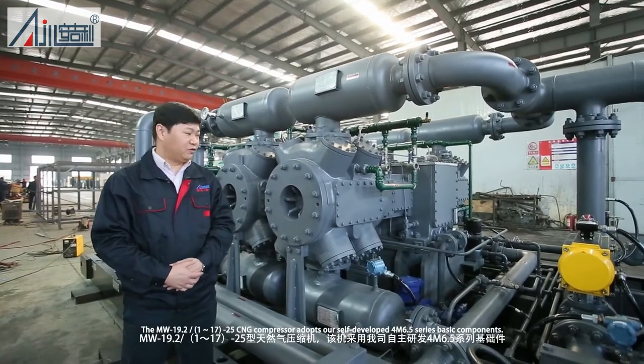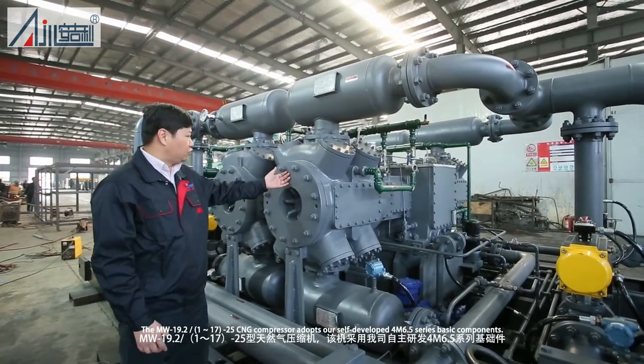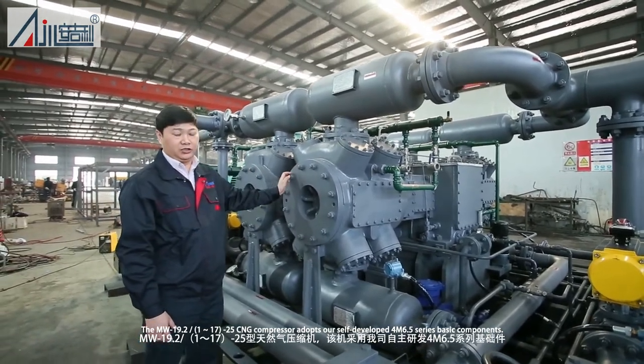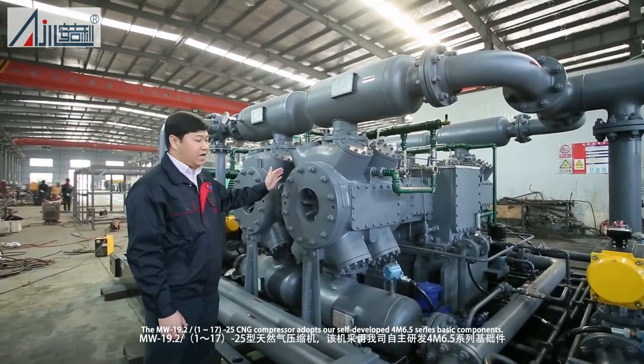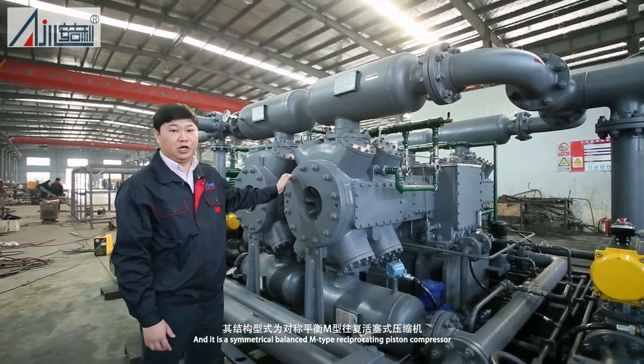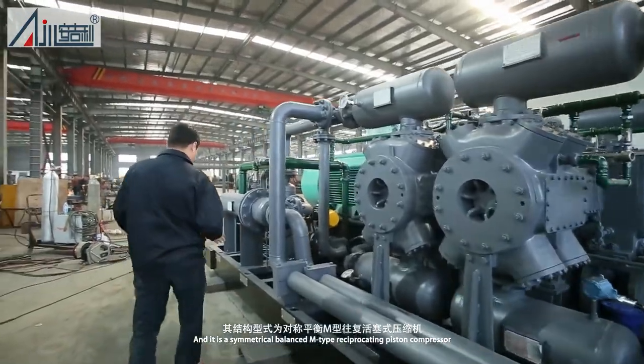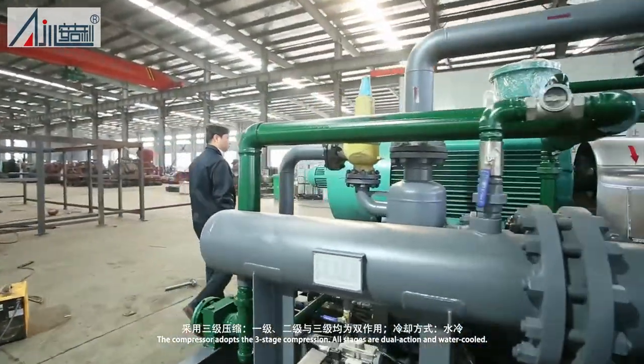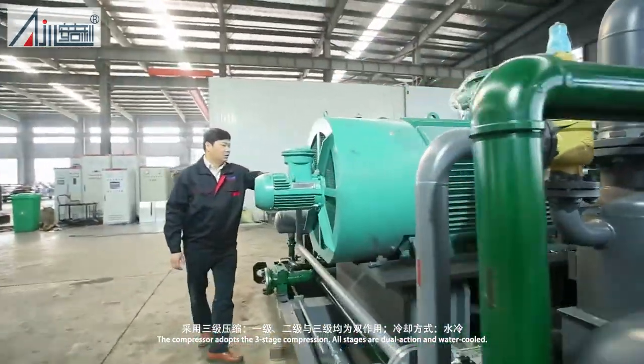The MW 19.2 1-17-25 CNG compressor adopts our self-developed 4M 6.5 Series Basic Components and it is a symmetrical, balanced, M-type reciprocating piston compressor. The compressor adopts three-stage compression. All stages are dual-action and water-cooled.